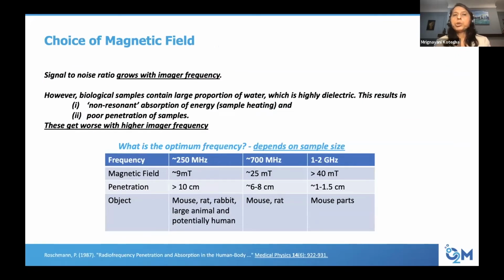A little bit about the choice of magnetic field. Signal to noise ratio grows with imager frequency. However, power absorption also grows with imager frequency. So we have to make a balance between getting the maximum SNR and maximum penetration depth. If we take 25 millitesla, which is about 700 megahertz, that's good enough for mice, rats, etc.